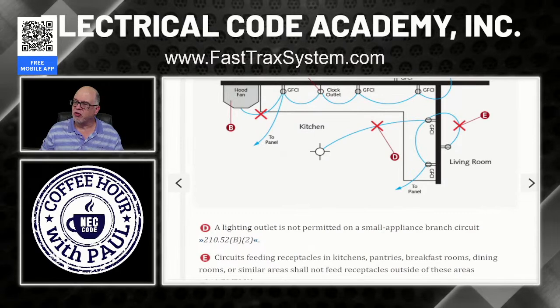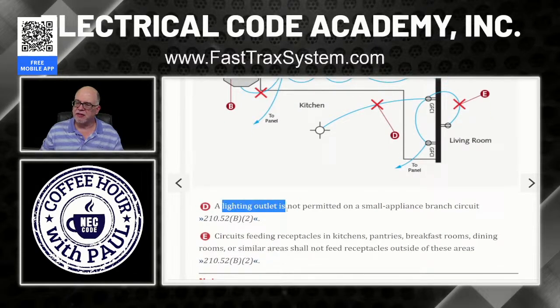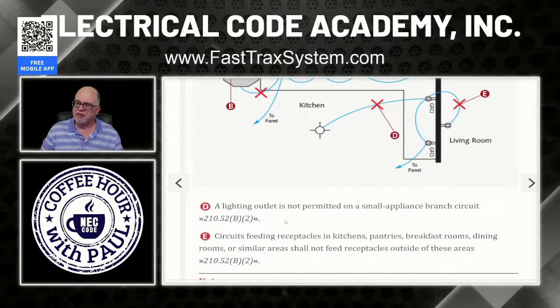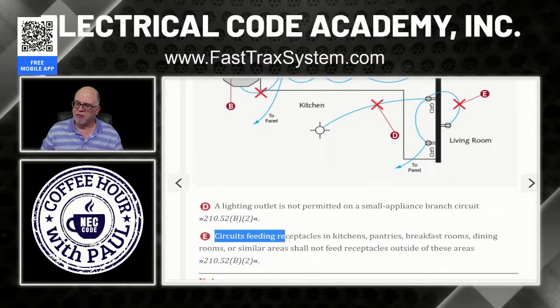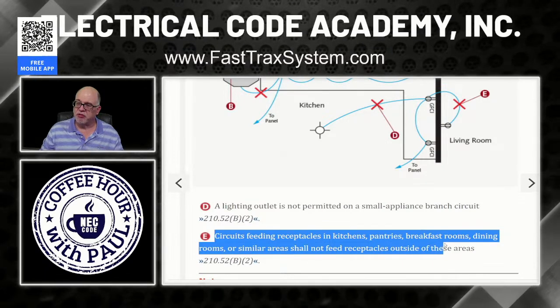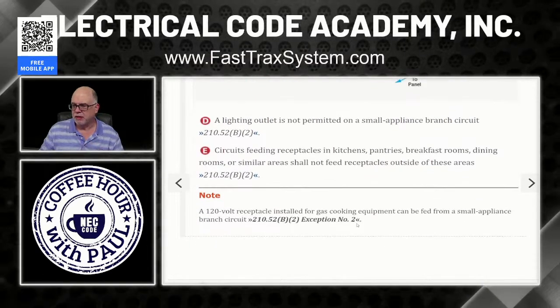Now here, just so you see things like D says the lighting outlet is not permitted on the small appliance branch circuit. We looked at that. And then E says circuits feeding receptacles in kitchens, pantries, breakfast rooms, dining rooms, and similar areas shall not feed receptacles outside of those areas. That's what those small appliance branch circuits are for. They're certainly not for feeding the living room. Okay, all that makes sense.